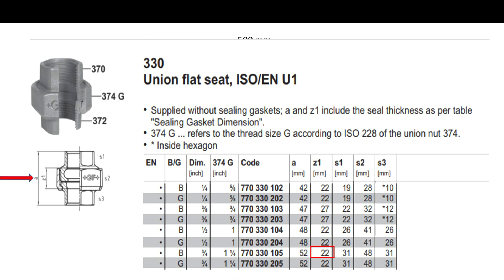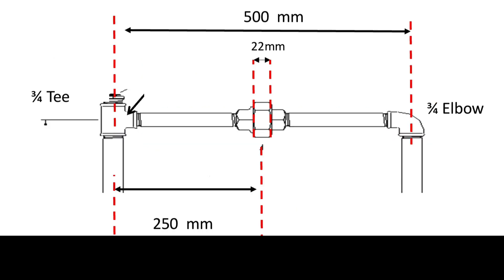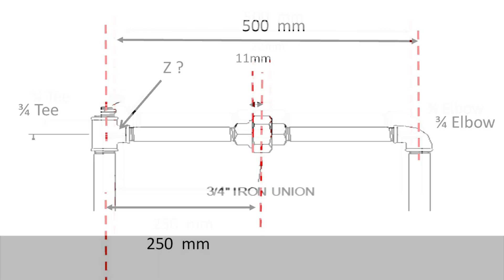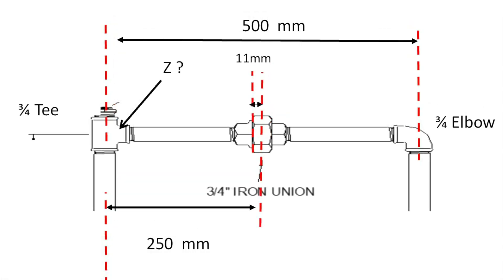Right, let's find the Z dimension for this union, which equals 22mm. Right, so let's take off half of that. So 250 minus 11 equals 239mm.